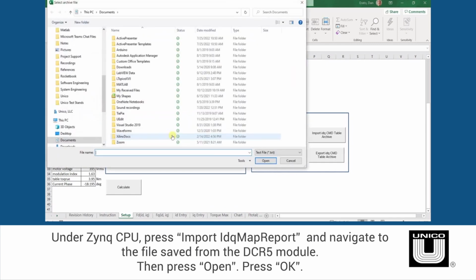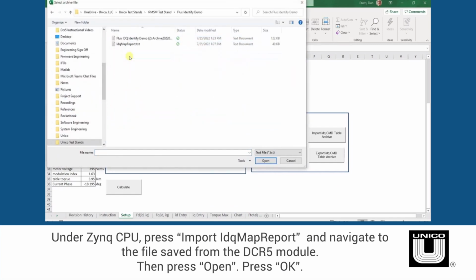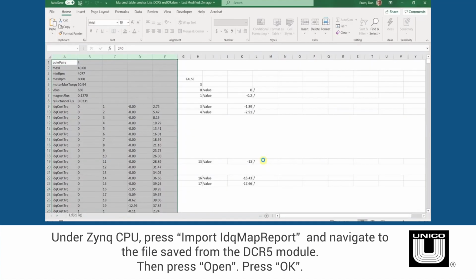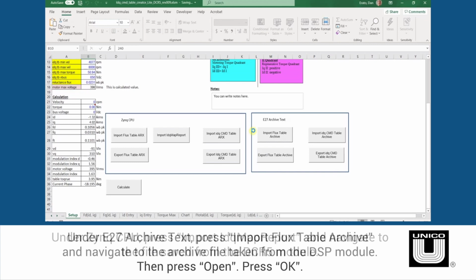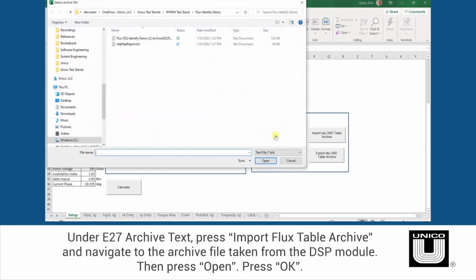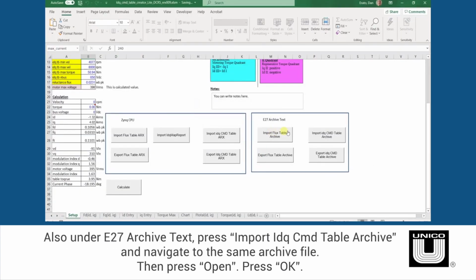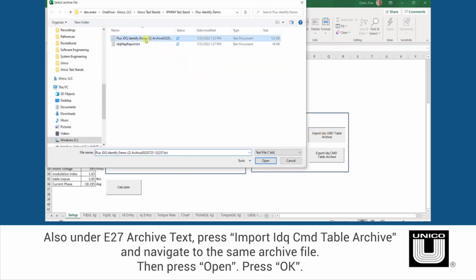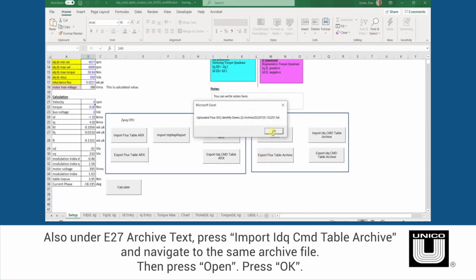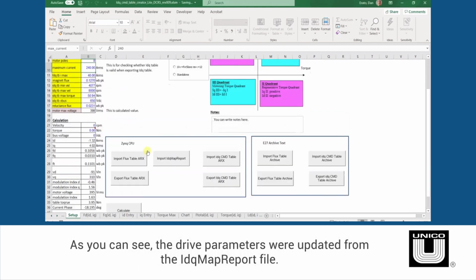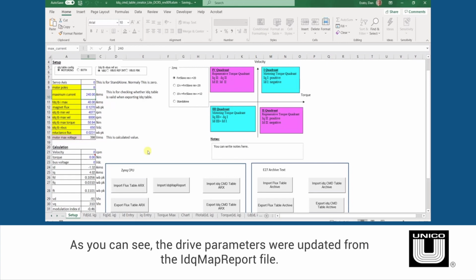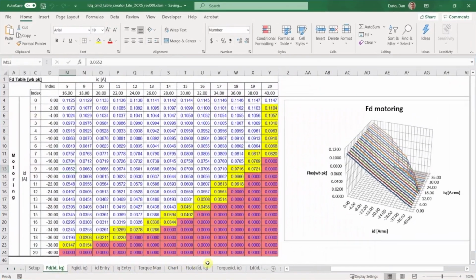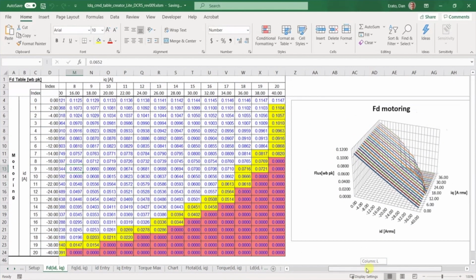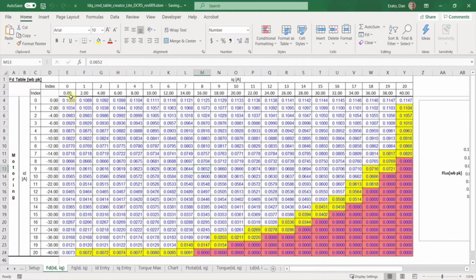So select the Import IDQ map report button and navigate to the file saved from the DCR5 module. Next, select the Import Flux Table Archive button and navigate to the archive file taken from the DSP module. Lastly, select the Import IDQ Command Table Archive button and navigate to the same archive file. As you can see, the drive parameters were updated from the IDQ map report file. Now I will highlight the important sheets in the IPM spreadsheet. The FD sheet shows the D-axis flux table as a function of the D-axis and Q-axis currents.